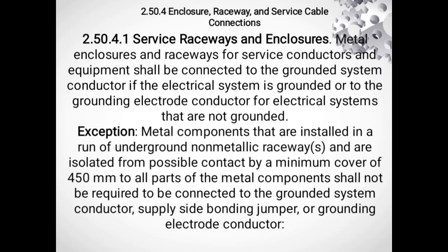2.50.4 Enclosure, raceway and service cable connection. Service raceway and enclosure. Metal enclosure and raceway for service conductors and equipment shall be connected to the grounded system conductor if the electrical system is grounded, or to the grounding electrode conductor for electrical systems that are not grounded. Exception: metal components that are installed in a run of underground non-metallic raceways and are isolated from possible contact by a minimum cover of 450 mm to all parts of metal components shall not be required to be connected to the grounded system conductor, supply side bonding jumper, or grounding electrode conductor.